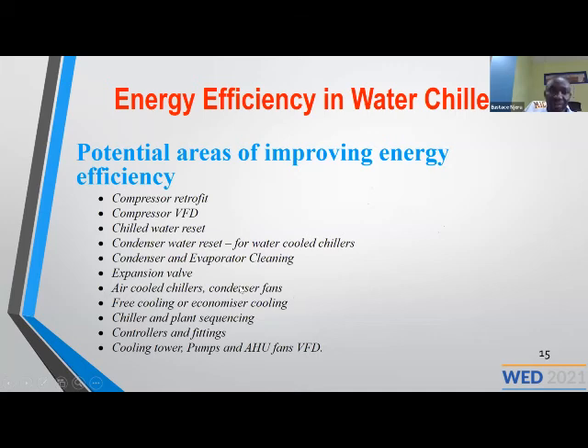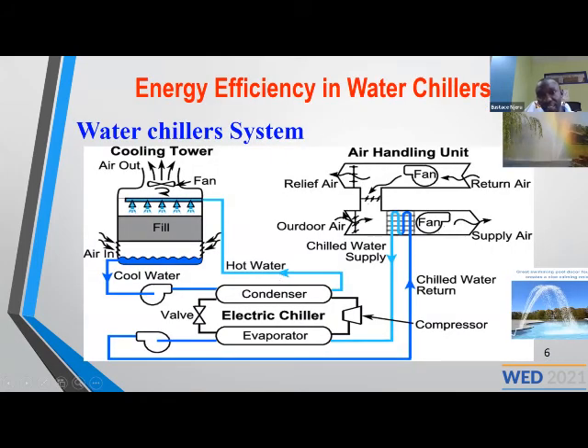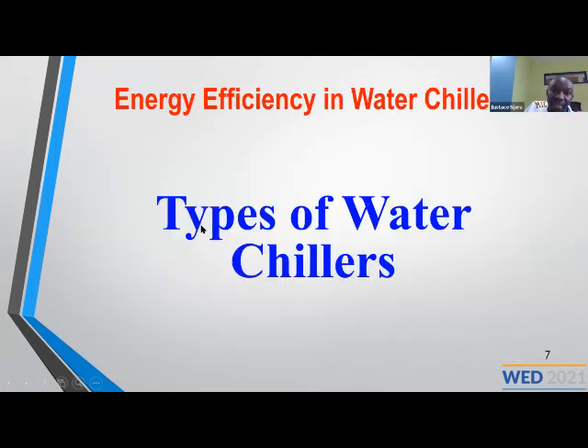The other one is you need to employ free cooling. In cases where the surrounding conditions are not very hot, instead of continuing running, especially for water-cooled chillers like this one, if the outdoor air temperatures are very low, you can cool the space, for example, using the air. And in such a system, you don't require very low temperatures here. And then sometimes you can even bypass the chiller, the compressor of the chiller, and use the water cooled in the cooling tower directly. I'm going to show you the next diagram later. So that's where you employ the free cooling.